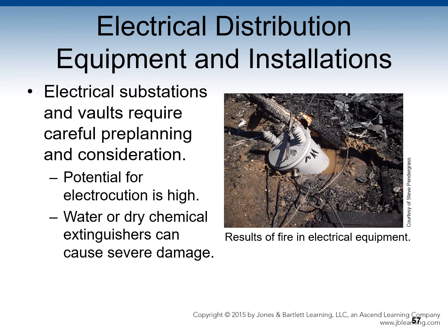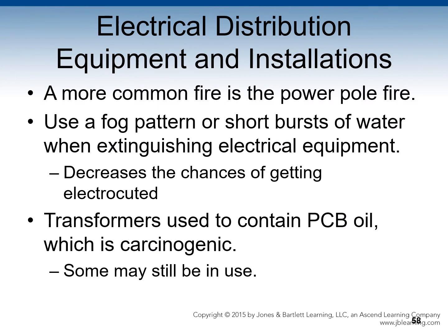It is also possible that indiscriminate use of water or dry chemical extinguisher could cause much more damage than the fire itself would. A more common fire is the power pole fire. Since water can conduct electricity, it is better to use a fog pattern or short bursts of water when extinguishing electrical equipment. This lessens the chances of getting electrocuted. Most transformers containing polychlorinated biphenyl (PCB) oil have been phased out. PCB oil is carcinogenic, but some of these transformers may still be in use.